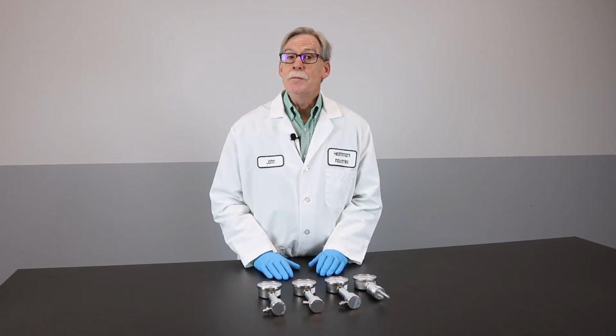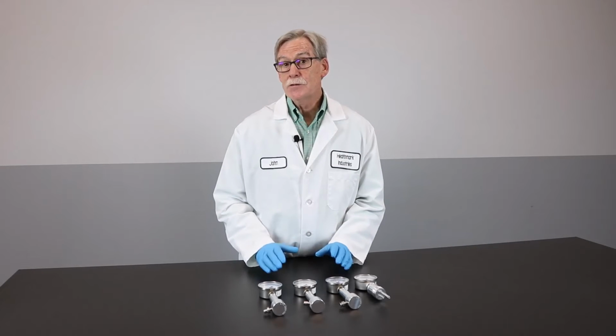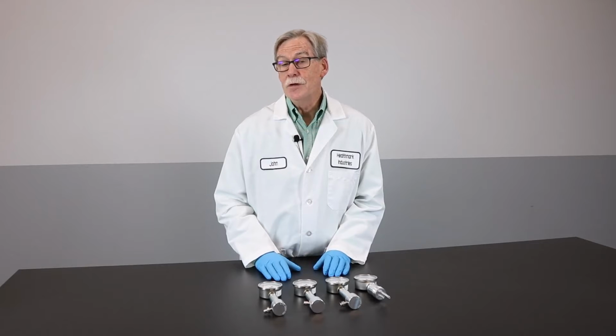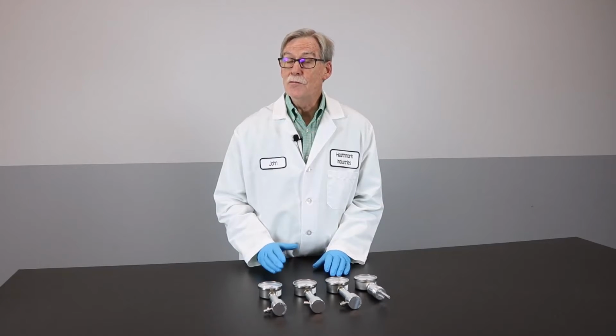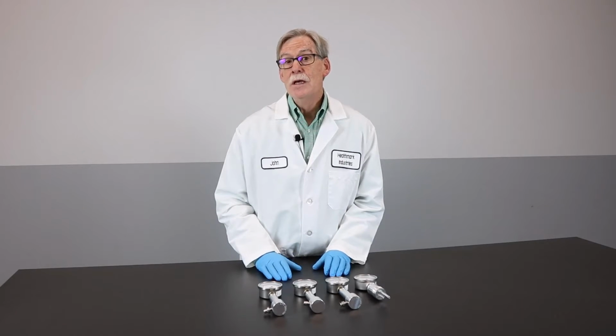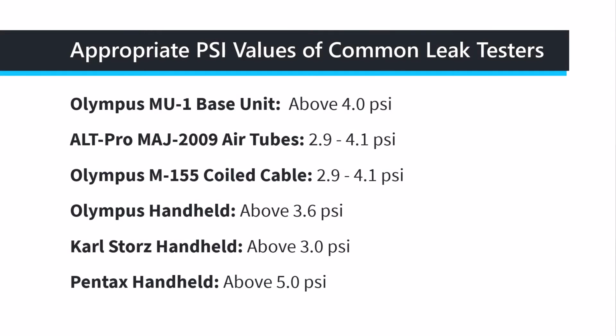So this video is for demonstration purposes only. In actual use, leak testers are used in a decontamination area, so you need to follow your facility's policies and wear appropriate PPE. So each leak tester has an appropriate PSI value, and you want to reference the IFU for the leak tester to be able to tell from one brand to the next what the correct PSI reading should be.